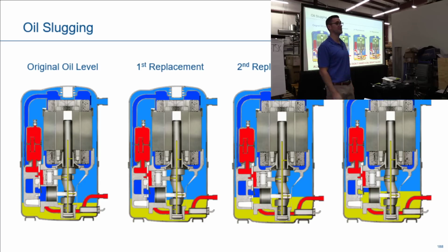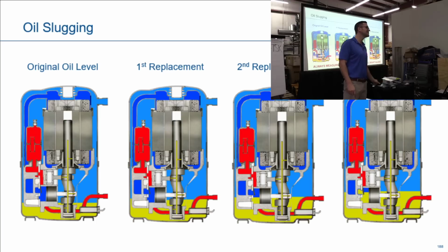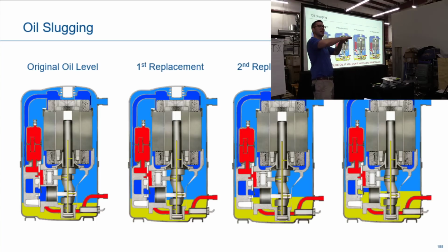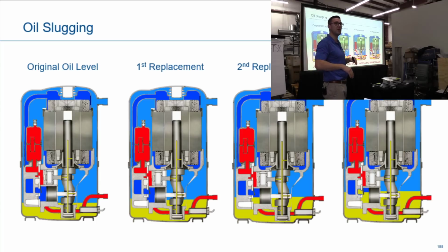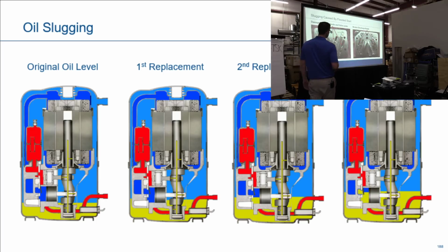Logged in 1 coil. I'm like, whoa, that's pretty cool. So we went up and we checked, and whoever installed it on this one here, which way should your suction line flow? Towards the evaporator or towards the compressor? Towards the compressor. So we had to fix that problem.